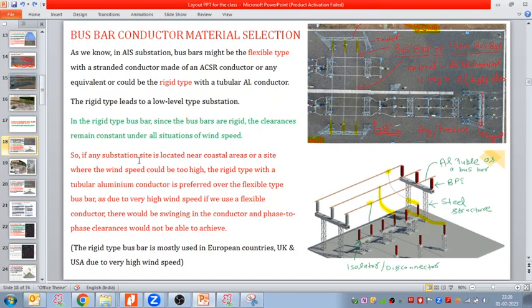Now let us implement this point in the substation. If any substation site is located near a coastal area or a site where the wind speed could be too high, the rigid type with a tubular aluminum conductor is preferred over the flexible type bus bar, due to very high wind speed. If we use flexible conductor, there would be swinging and phase-to-phase clearances would not be achieved. So if your site is near the coast, near the sea, or any site with higher wind speed, go with the rigid type bus bar.